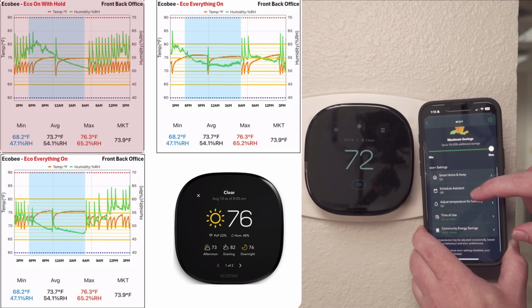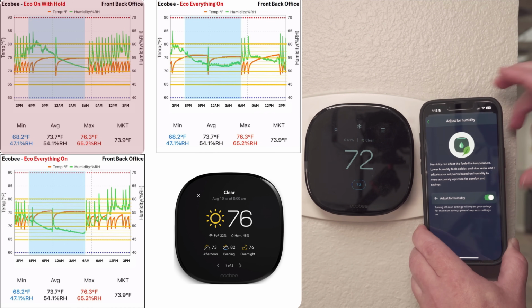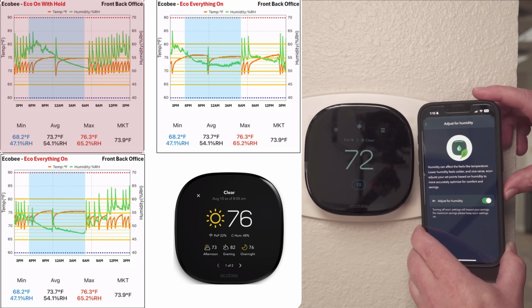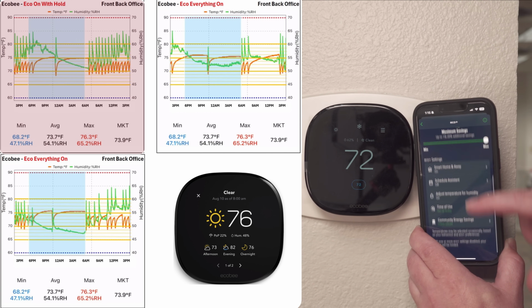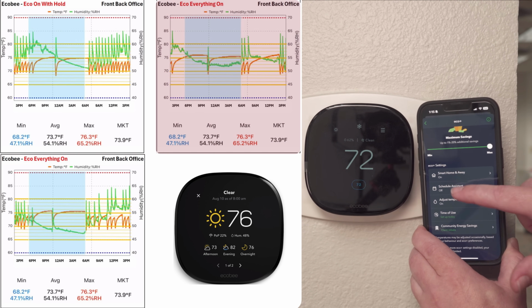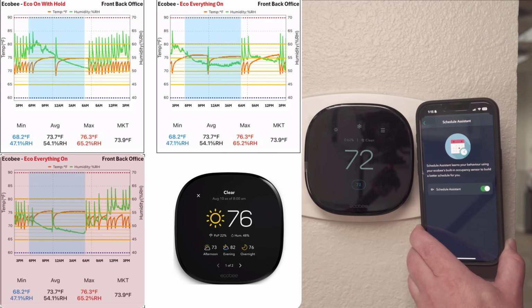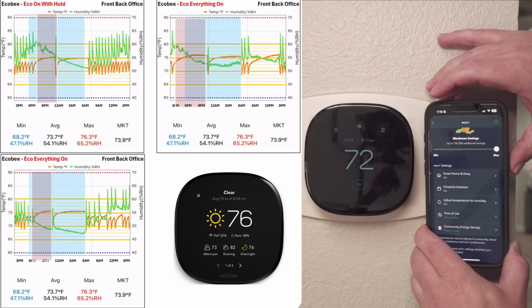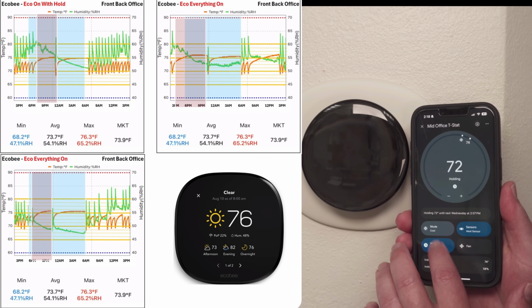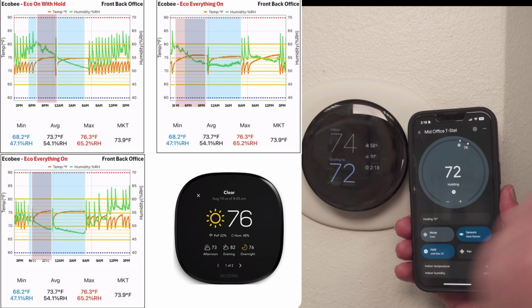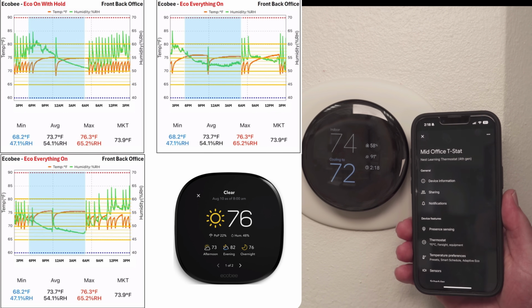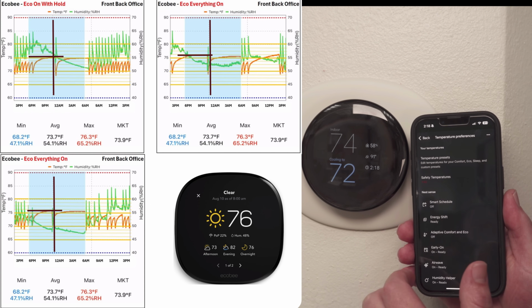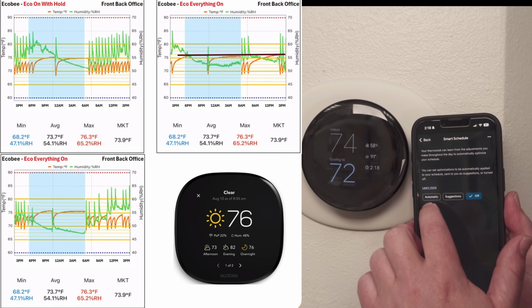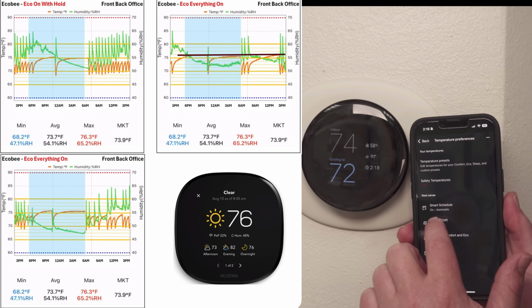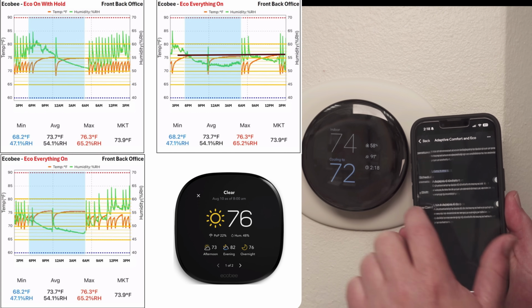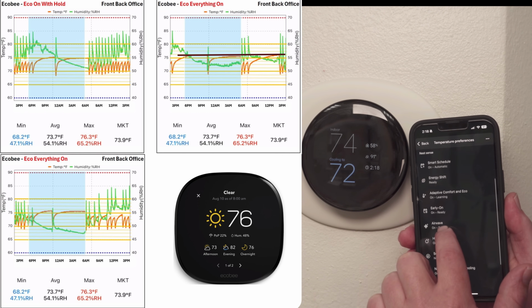Here's 3 days of data for our Ecobee. The first graph I'm reusing from the comfort section, where I put a hold on the thermostat without making changes, and apparently it went into eco mode. The next graph is a Sunday with the office vacant, and the last one is that next Monday. The biggest thing to note is these sections, because the schedule is set to run until 11:30 then go into sleep mode at 76 degrees. You can see it's not maintaining 72 degrees until 11:30, so when there are no occupants, the temperature adjusts back up to 76 degrees. Over here is the Sunday, where it basically maintains 76 degrees throughout the entire day. I also have away mode set at 82 degrees, so I'm not really sure why it's maintaining around 76.